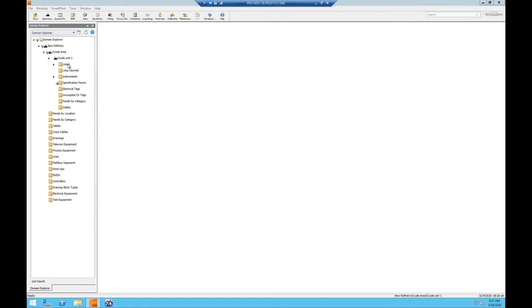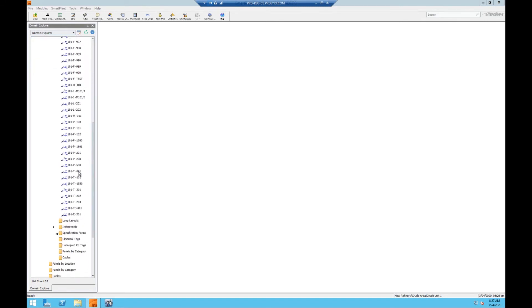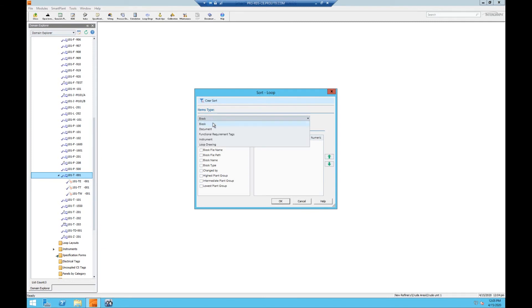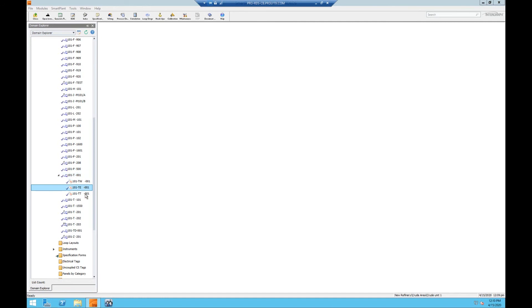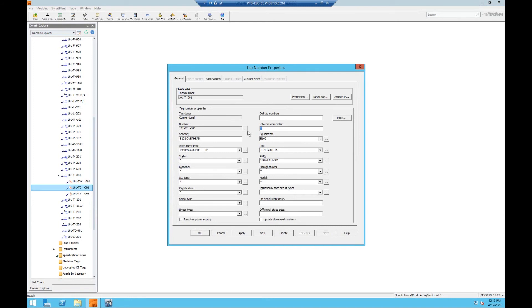If we go to the Loops folder and click Refresh, we will see that our tag has been assigned to loop T-001. Note: the default order of your tags in your loop is set to alphanumeric. If you want to organize the order of your tags by internal loop number, you can right-click the loop and click Sort to open the Sort window. We can change the item type to Instrument and check the box for Internal Loop Order. If you need to update the internal loop order, right-clicking and clicking Properties will open the tag number properties window where we can update our internal loop order.